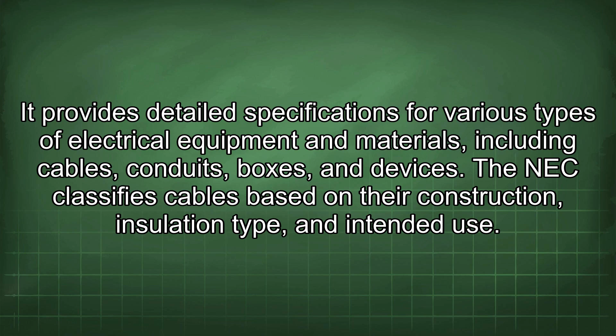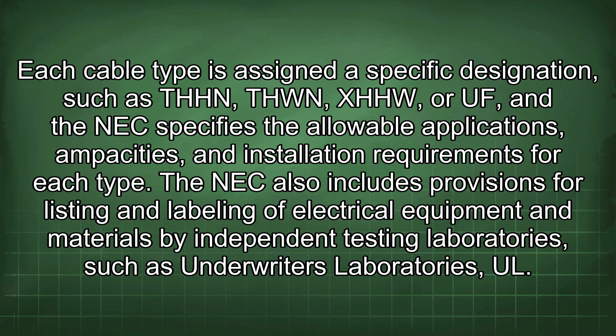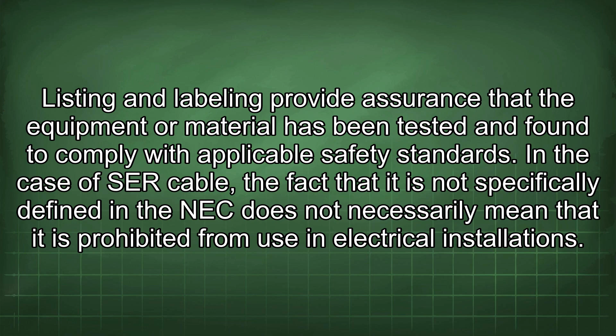The NEC also includes provisions for listing and labeling of electrical equipment and materials by independent testing laboratories such as Underwriters Laboratories, UL. Listing and labeling provide assurance that the equipment or material has been tested and found to comply with applicable safety standards. In the case of SER cable, the fact that it is not specifically defined in the NEC does not necessarily mean that it is prohibited from use in electrical installations. However, it does mean that the NEC does not provide specific guidance on its installation or use.